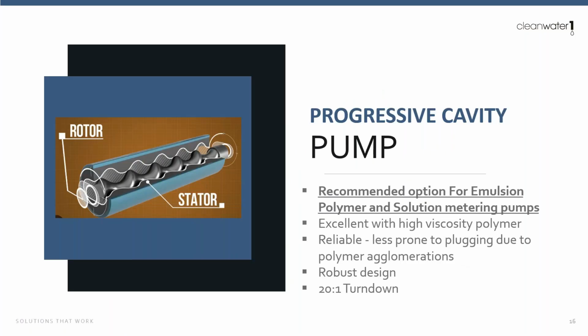The recommended option for emulsion polymer and solution metering pumps for dry polymer is progressive cavity. These are excellent with high viscosity polymers when we're in reference to a neat polymer. They're really reliable, less prone to plugging due to polymer agglomerations, and those can be naturally occurring agglomerations in your neat polymer supply. So they do a really good job of passing those agglomerations without plugging. The other benefit of these, you have a really robust design, and then you do get a pretty good 20-to-1 turn down out of these pumps.